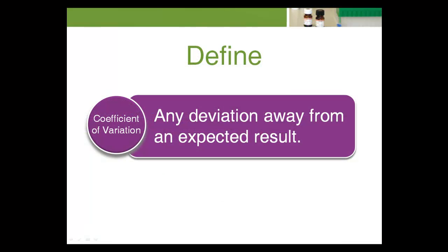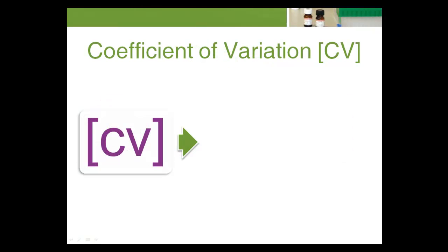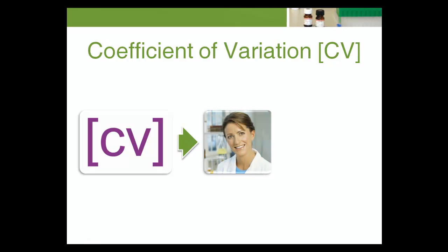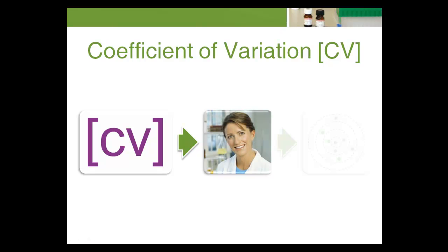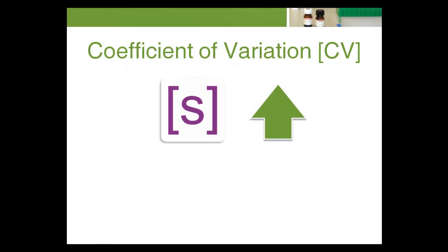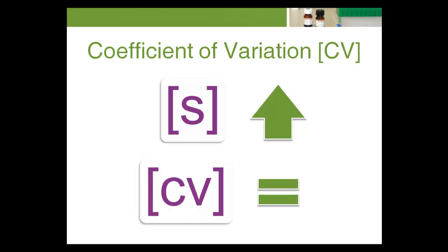Let's begin with Coefficient of Variation. CV is the ratio of the standard deviation to the mean and is expressed as a percentage. The CV allows the technologist to make easier comparisons of overall precision. Since standard deviation typically increases as the concentration of the analyte increases, the CV can be regarded as a statistical equalizer.